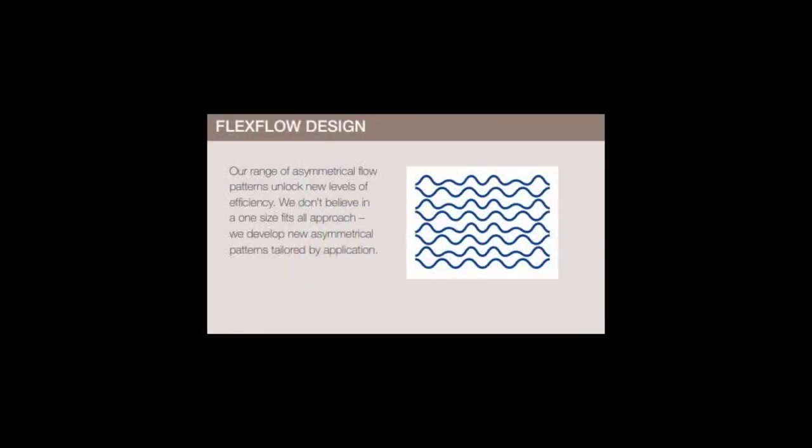As you can see, there is no size that fits all. And on top of all these options — the different thetas and the pressing depth — Alfa Laval has asymmetrical plates. Asymmetrical plates are designed to solve one of the most common problems in plate and frame heat exchangers: the fact that the two sides preferably should have the same flow rate. If you have different flow rates on the two sides, you can actually take advantage of the asymmetrical plates and have a shear stress which is good on both sides.